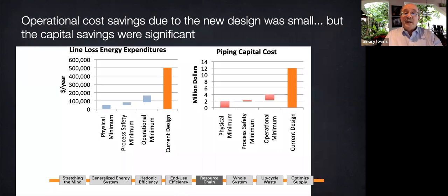But most interestingly, the capital cost of the piping shrank by 2/3. You may recall that piping was 36% of the entire capital cost of the unit. So this preliminary exercise made the unit about 1/4 cheaper to build, which is really news in that industry. Now, with more effort, we could do better, but this was a promising start. And we're not even counting the value of the saved space, which for another client's floating hydrocarbon facility turned out to be extremely valuable. And that revealed some novel compactness opportunities that are now also being exploited on land.